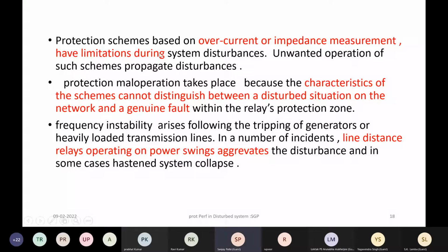We talked about the protection scheme based on overcurrent and impedance principle. Both have limitations during system disturbances. Settings-wise and characteristic-wise, again, there is a recommendation. The relay should be able to detect a fault condition and distinguish it from a power swing type of situation, which is a disturbance event, but which can be recoverable. It is a recoverable swing.